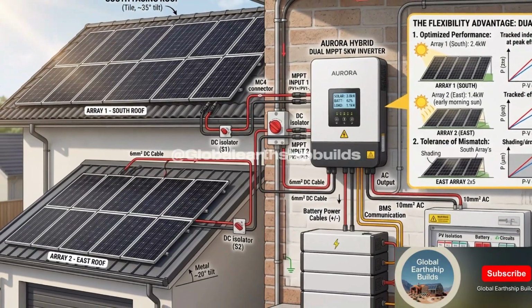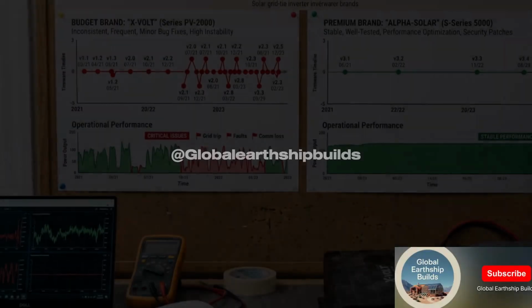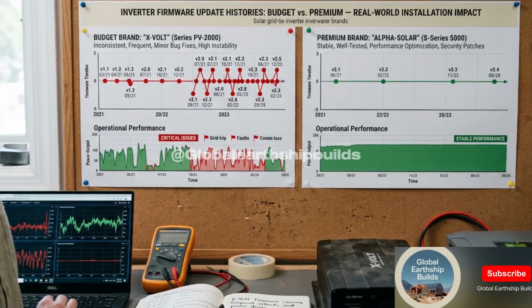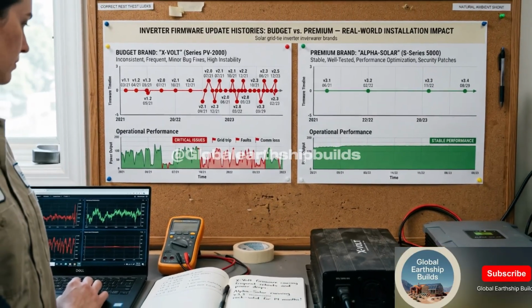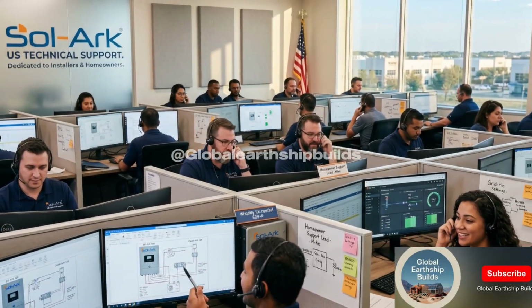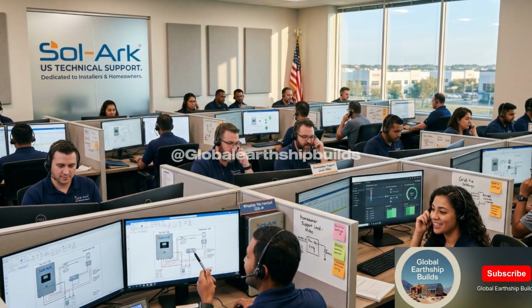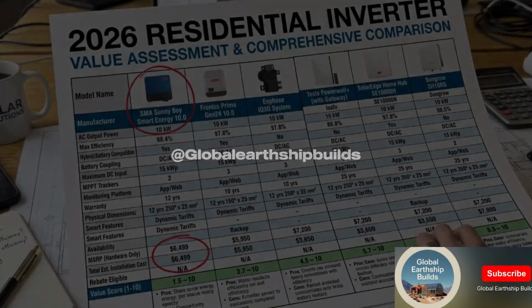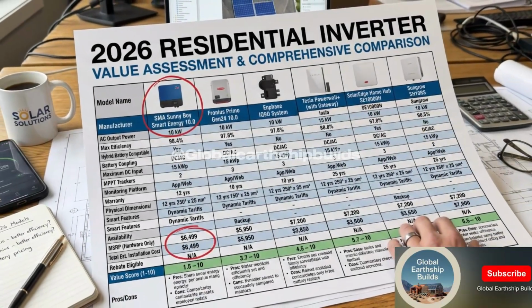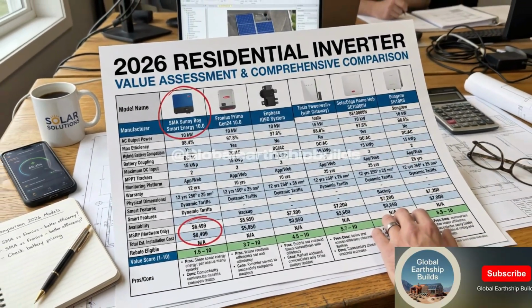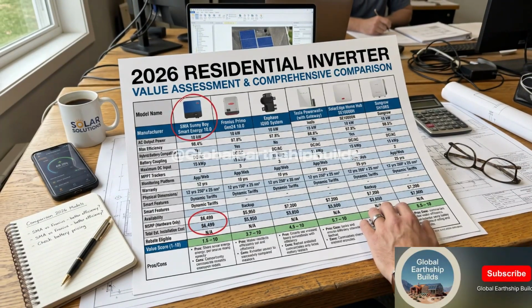The trade-off is surge capacity. A hybrid inverter, especially a transformerless design, will typically surge to 1.5 to 2 times its continuous rating. A good transformer-based off-grid inverter can surge to 2.5 to 3 times or more. If you are starting motors and running heavy loads that pull hard on startup, that difference matters.